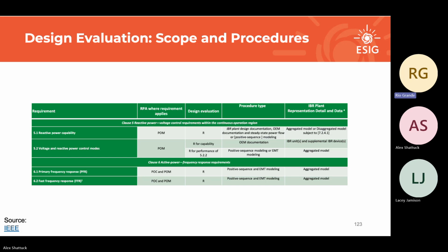Maybe not. Most of the time, how do you build an aggregated model? You build a disaggregated model first, most of the time in some manner, right? You're either building it in PSSE, or you're putting it in a spreadsheet and running a script. You've already done the work to build a disaggregated model. When I was doing it, our script was just, I check a box for both or I check a box for one. And that was the difference of work between the two. So could be a good way.